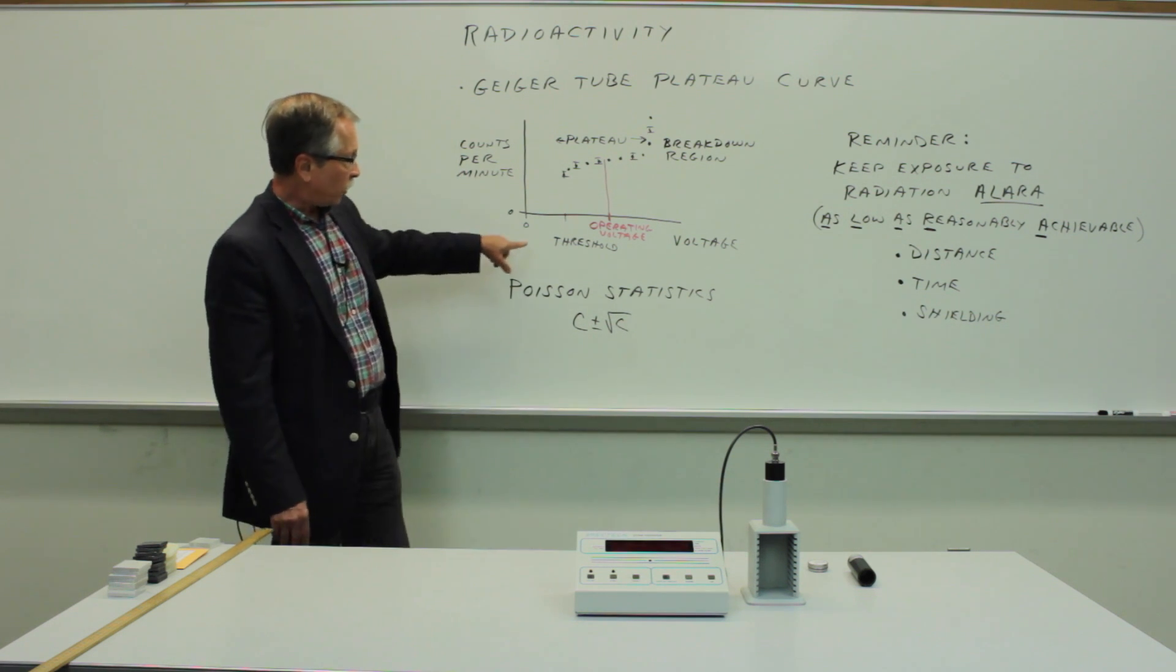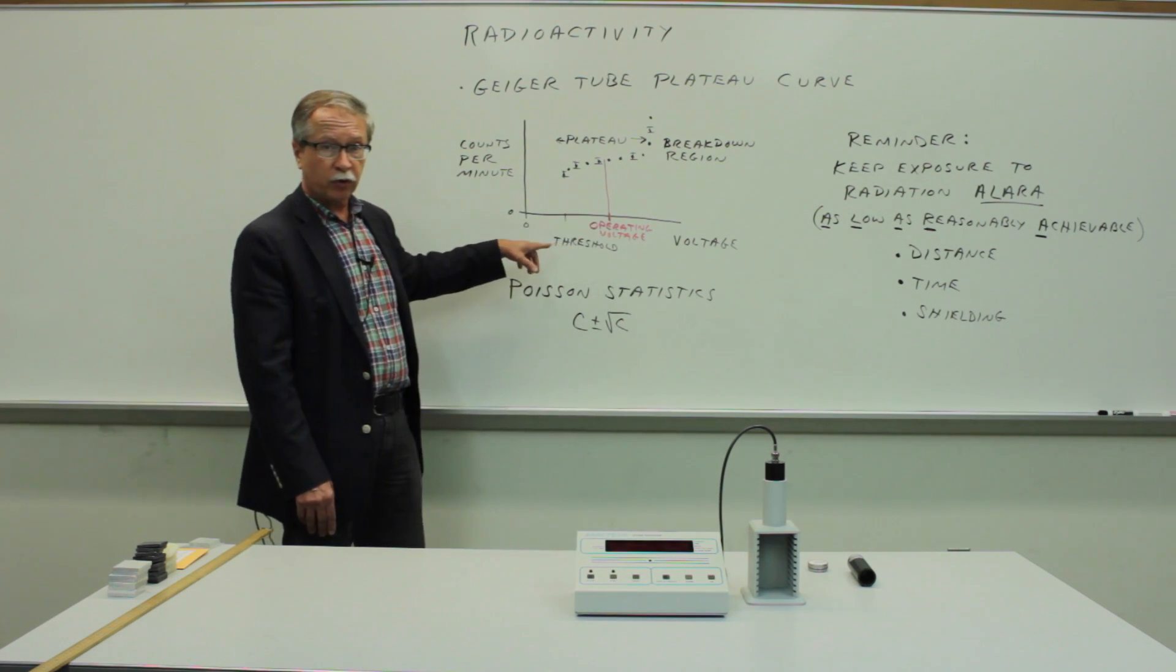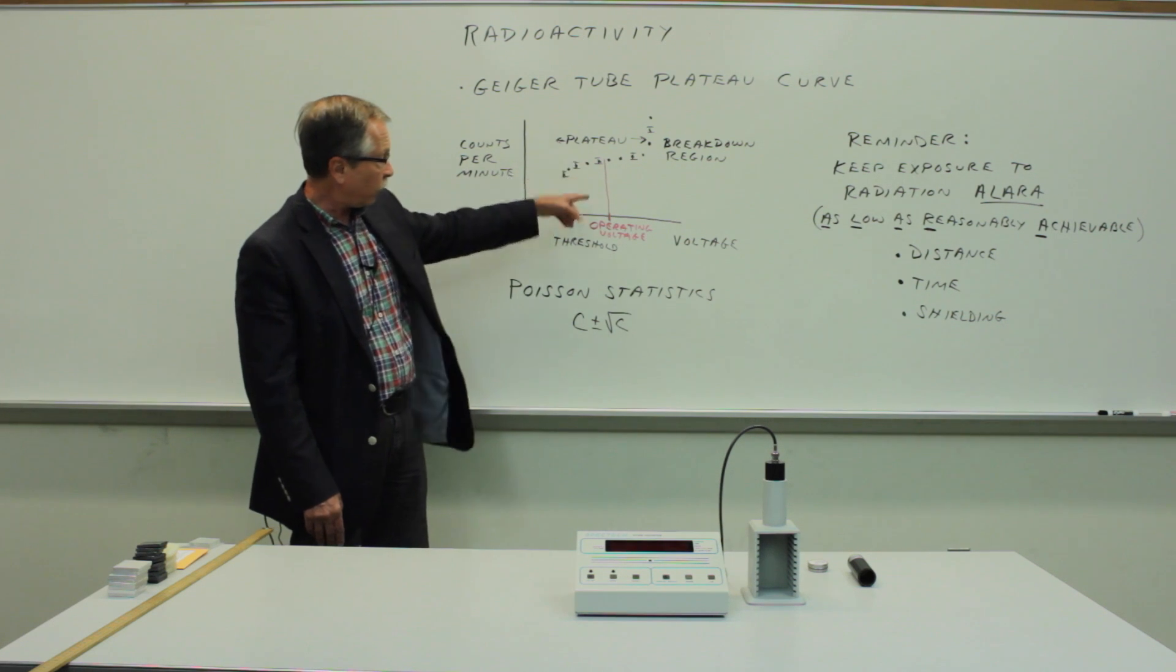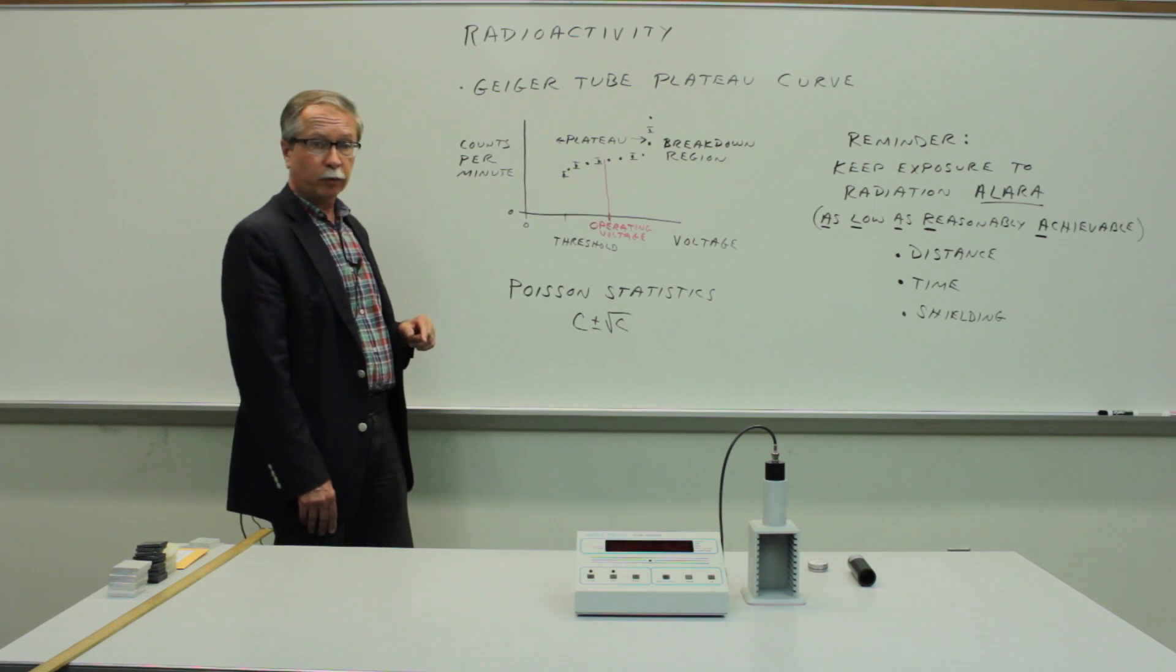We'll plot the number of counts as a function of the voltage applied to the tube and use this information to determine what the best operating voltage will be.